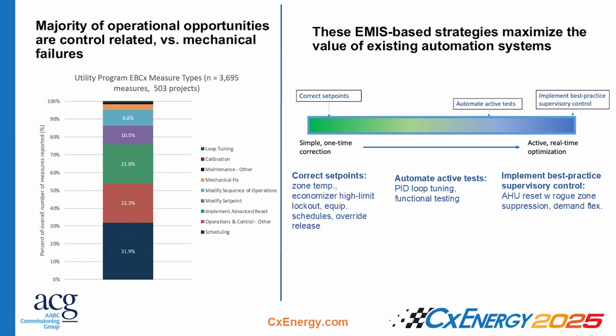So controls faults that are associated with things like schedules running too long or too short, set points being too low or too high, overrides being in place for months. These faults are not only pretty common, but also can lead to the most energy waste, especially things like scheduling. It makes sense, right? If things are running too long or too short, some systems are running 24/7, you're going to see a lot of energy waste that you could fix right away. So we're thinking now about these FDD tools not just as passive observers, but we're really trying to get to a point where we're seeing these tools as having the ability to write back and fix the fault at the point of potential detection.